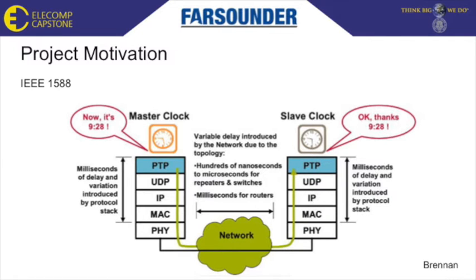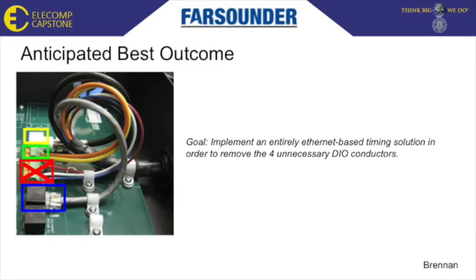PTP1588 works by setting up one device as a master clock and one device as a slave clock. The master constantly reminds the slave clock of the current time with very little delay, keeping the devices in sync. Our anticipated best outcome is the implementation of an entirely Ethernet-based timing solution and the removal of the 4 unnecessary digital in and out conductors.